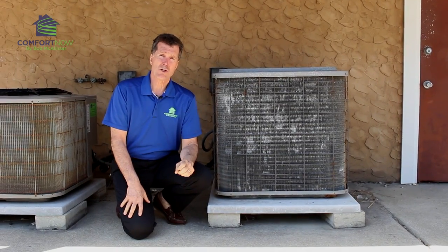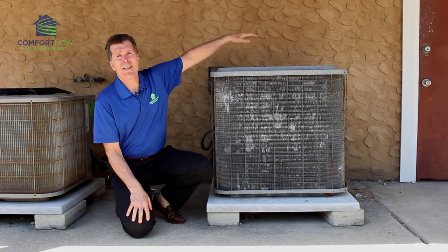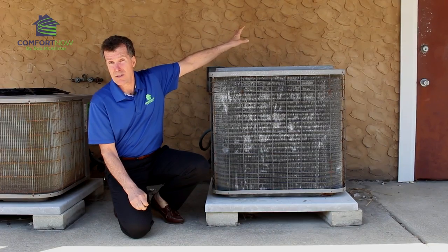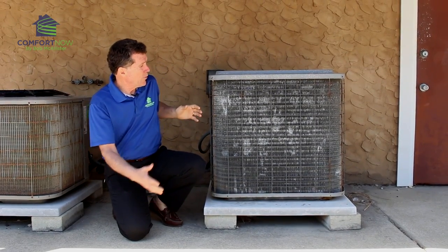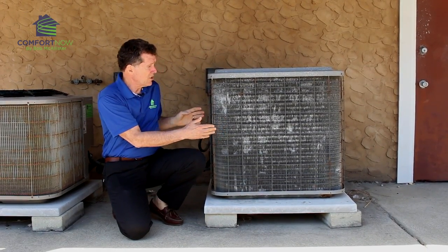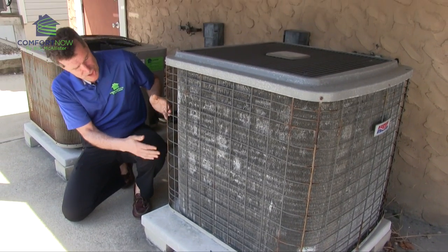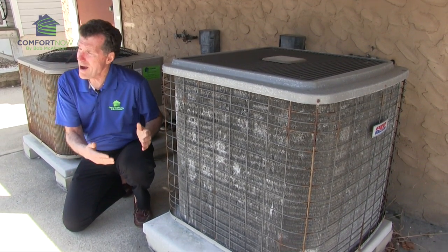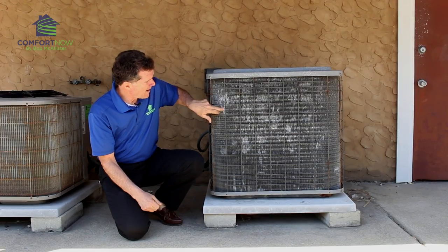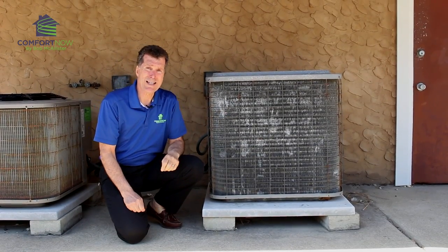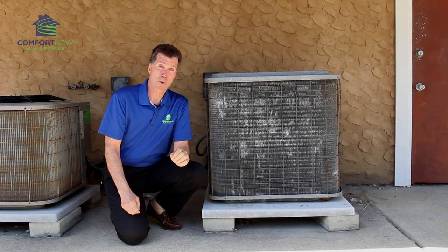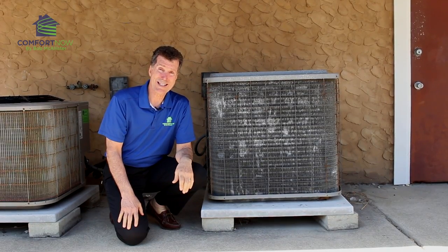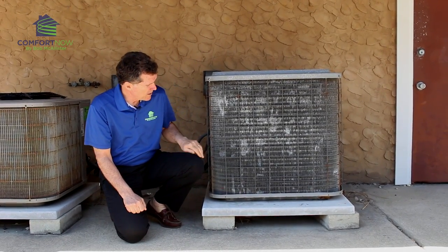You know from your air conditioner, if you walk by it in the summer, heat comes out of the top, that's the heat from inside your house being exchanged through the air that flows into the unit. Well, this thing is so blocked up, there's probably very little air getting through anymore. So not only have we lost capacity, but it's costing a lot more to operate the system in this condition. This unit is really due to be replaced.